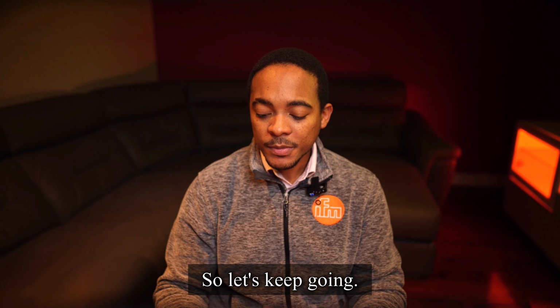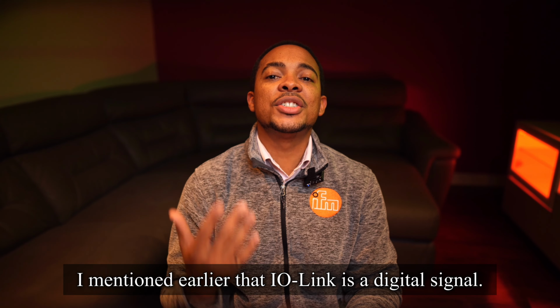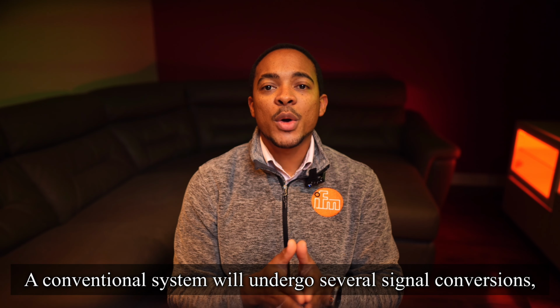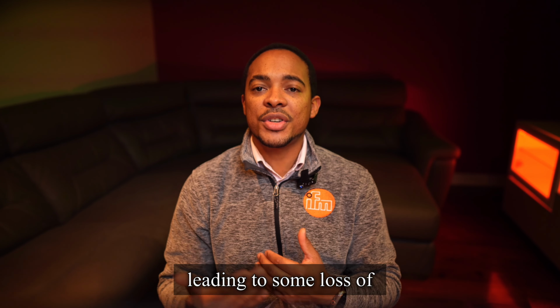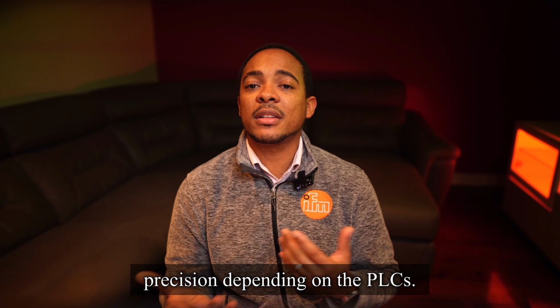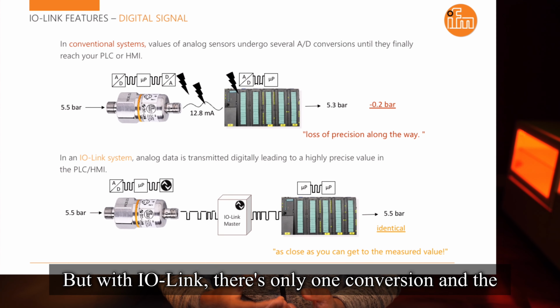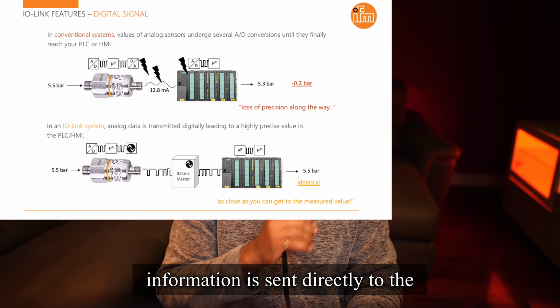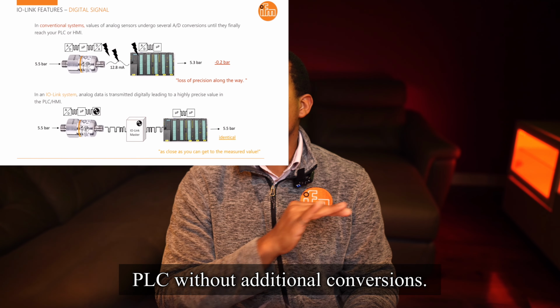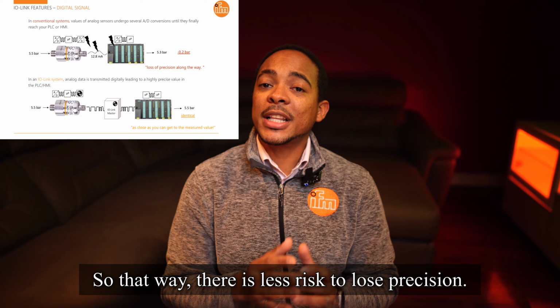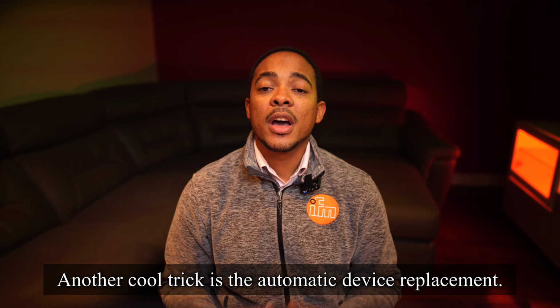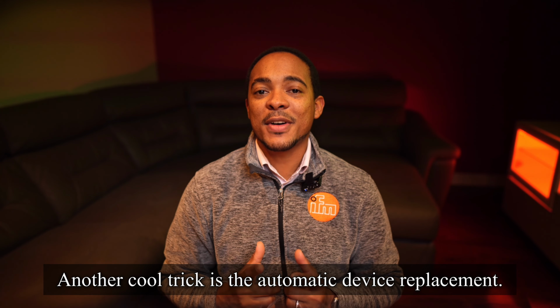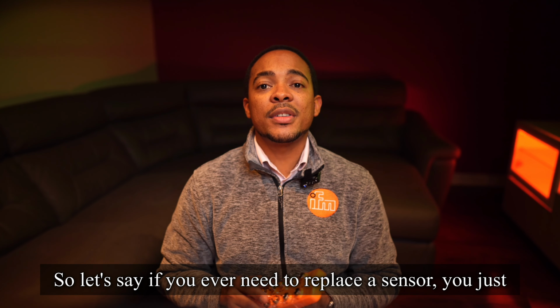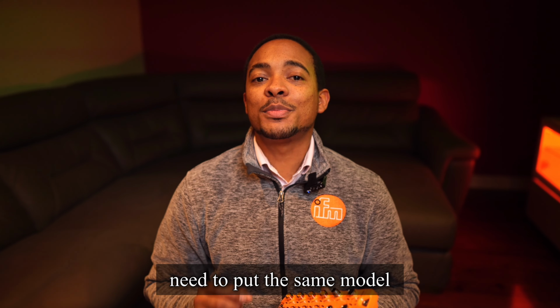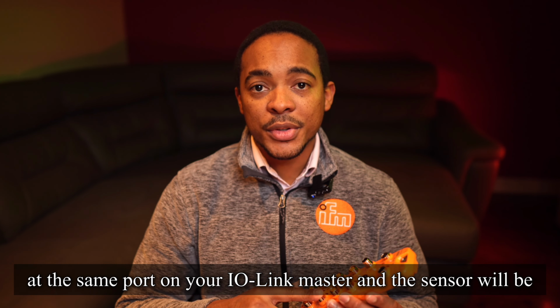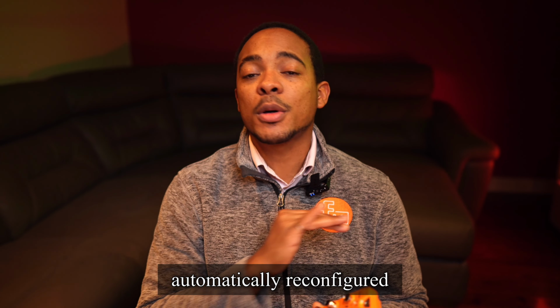So let's keep going. I mentioned earlier that IO-Link is a digital signal. A conventional system will undergo several signal conversions, leading to some loss of precision depending on the PLCs. But with IO-Link, there's only one conversion and the information is sent directly to the PLC without additional conversions. So that way there is less risk to lose precision. Another cool trick is the automatic device replacement. So let's say if you ever need to replace a sensor, you just need to put the same model at the same port on your IO-Link master and the sensor will be automatically reconfigured for you.